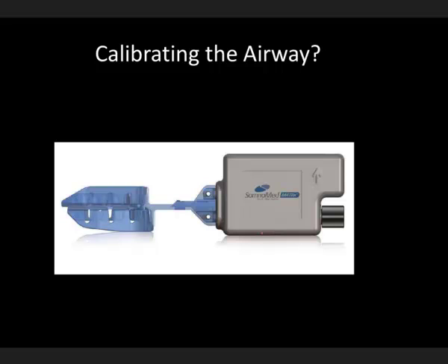Now, here's an interesting device. You probably haven't seen this one much yet. This is called MATRx. It's made by Zephyr Technologies, marketed by one of the companies, SomnoMed. What happens here is the patient comes to the dentist. These are semi-custom trays. We make a retainer over the teeth. They sleep with this. This box hangs out of their mouth. It weighs only about 20 grams, so it's not a big deal. And it's hooked up to the technician's console.